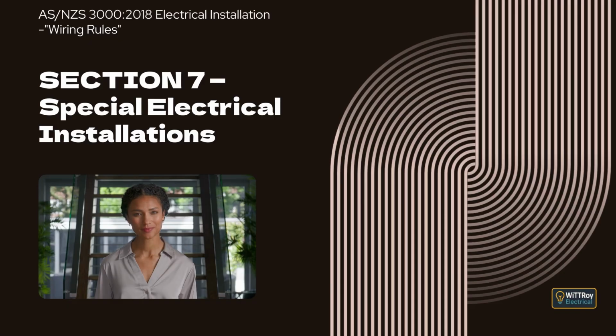This clause explains that an extra low voltage electrical installation must be controlled by one or more main switches that operate in all unearthed conductors. The purpose is to ensure the supply can be safely disconnected when required. It also explains that this requirement does not apply where the extra low voltage installation is supplied from part of a higher voltage installation and switching the higher voltage main switch disconnects the supply to the extra low voltage system.